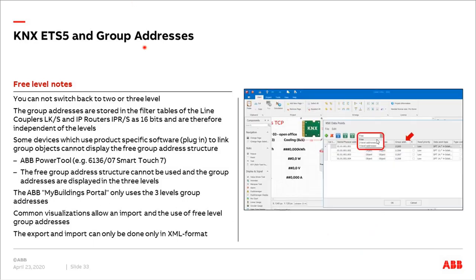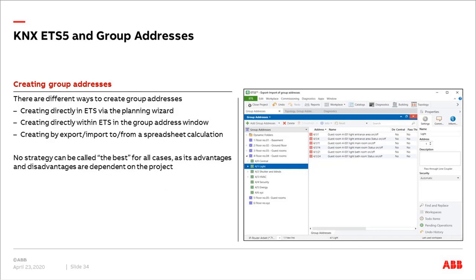The ABB My Building Portal — used for voice control or control touch configuration — only supports three-level group address range, though this may change in future. Most visualization and BMS systems on the market can import ETS projects in all three styles; when importing you can select free, two-level, or three-level. One limitation: export and import in free address style is only possible in XML format, not CSV — CSV is covered later as the easier option for Excel editing.